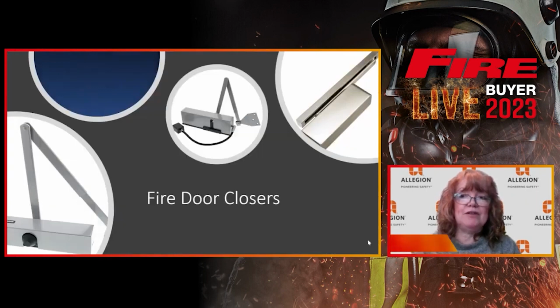As said earlier, a fire door consists of many components, but when it comes to its operation, a fully functioning door closer is essential. A fire door only prevents the spread of flames and smoke if it is fully closed. Relying on building users to do this 100% of the time is not realistic, so door closer technology is built to help with this. The main reason for disconnecting a door closer is that it's not suitable for the environment or the users.